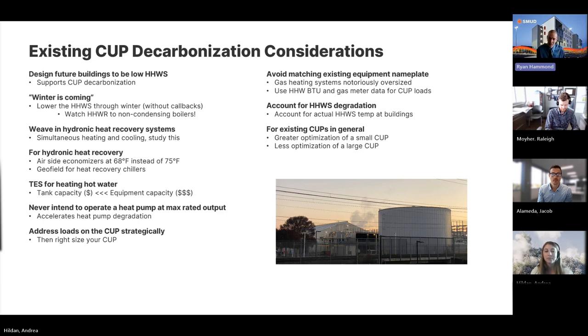But you want to study your system, because if you already have a chilled water plant, thermal energy storage on, you might have your chiller running where it's non-coincident, and so that would be something you want to study. Anyways, for hydronic heat recovery, and I will jam through this, consider air side economizers on your buildings, lowering it from 75 to 68 degrees outside air, and it brings up this idea that was mentioned earlier of false loading your central plant. And why would you want to do that? It's a way to recover valuable heat. And then, like Jacob mentioned with the geofield for your system, you could consider a geofield for heat recovery chillers to also false load them. Dump chilled water to recover valuable heat out of the earth. Use that heat into the rest of your campus.